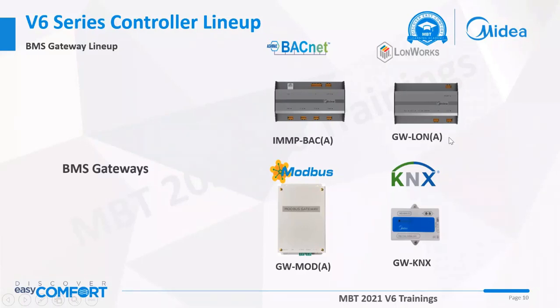This GW-LON(A) has only one XY port and it can connect 8 systems and 32 indoor units. Okay, this one can connect 32 indoor units. And again for the Modbus, here we have only one XY port. It again connects from the outdoor unit side and it can connect 8 systems and 64 indoor units. And this GWKNX connects to the indoor unit side, and each indoor unit needs to connect one KNX gateway. So these are the connection options for the BMS gateways. Mostly what we can say is that we have covered all major BMS protocols: LonWorks, Modbus, KNX, BACnet, all four are covered.